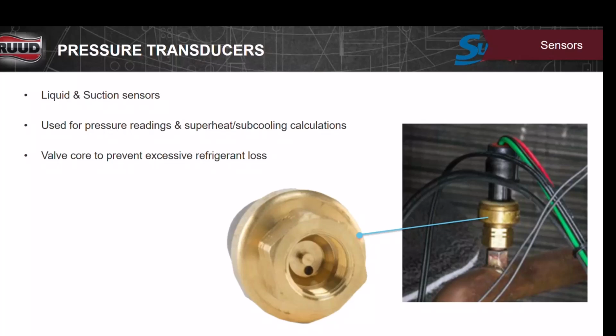So that's going to change what the expansion valve does, right? I pulled it off. The salesman was with me. I said, hey, go down the branch and get a new pressure transducer. While he was fixing to leave, I was taking it off, and I didn't hear any pressure come out when I took it off. So I shined my light inside there where the Schrader valve was. The Schrader core stem was bent. Oh, wow. So when you screwed this down, it wasn't touching the Schrader all the time. So if you turned it off, temperature difference would make it push it, and it would put pressure on it. So I had 90 pounds on it, but inside the coil was actually 150 pounds, right? So there's just little things to look at, because that caused 2 compressors to go out.